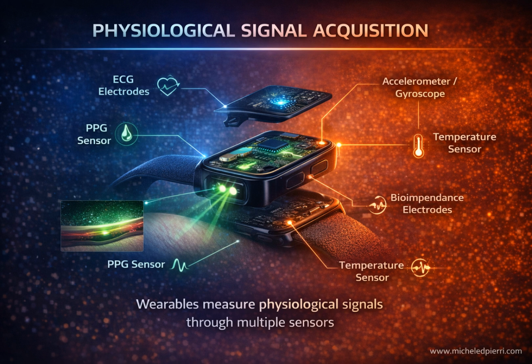Inertial sensors such as accelerometers and gyroscopes measure motion and posture. They help identify when physiological signals are corrupted by movement. Temperature sensors provide additional context. Skin temperature differs from core temperature, but its trends can reveal physiological changes. Bioimpedance sensors estimate tissue resistance by injecting a tiny current. This can provide information about fluid shifts or respiratory variation. The key idea is simple. Wearables do not measure diseases. They measure physiological signals. And every signal is imperfect, influenced by physiology, hardware design, and noise.